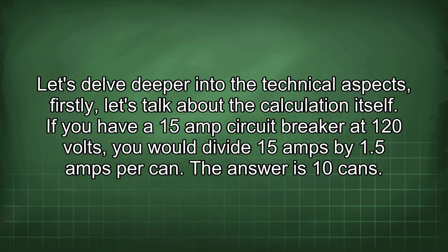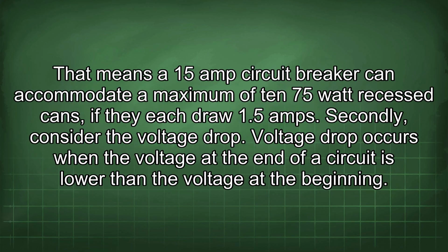Let's delve deeper into the technical aspects. Firstly, let's talk about the calculation itself. If you have a 15 amp circuit breaker at 120 volts, you would divide 15 amps by 1.5 amps per can. The answer is 10 cans. That means a 15 amp circuit breaker can accommodate a maximum of 10 75-watt recessed cans if they each draw 1.5 amps.